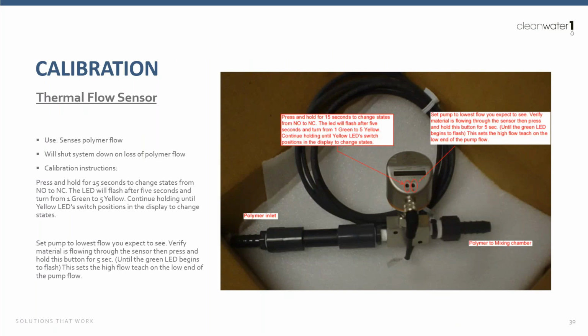Another really important aspect of these is because it's another pinch point, they need to be cleaned. Cleaning frequency depends on a whole bunch of different factors, right? Type of polymer being used, amount of agglomerations in it. These are really easy to clean. They basically thread out, you wipe them down, you place them back in. A lot of the times when we see issues with system faults or something like that, it's this guy needing to be cleaned, and it's a really easy fix. So something to keep an eye on, as well as being able to calibrate this thermal flow sensor.